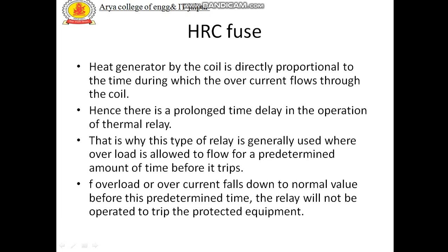Its heating element is usually designed to withstand short time overload. Heat generated by the coil is directly proportional to the time during which the overcurrent flows through the coil. Hence, there is a prolonged time delay in the operation of the thermal relay. That is why this type of relay is generally used where overload is allowed to flow for a predetermined amount of time before it trips.